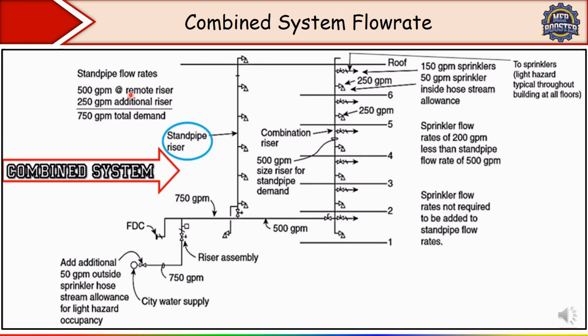You can also do the hydraulic calculation separately for the sprinkler system and for the standpipe. Now you have to see the flow value, whichever is larger, that we have to consider. No need to sum: the flow demand for sprinkler does not need to be summed with the standpipe demand. Whichever is greater, we have to consider. So is it clear? Now here you can see this 750 GPM is our total demand. As per that we have to do the selection. Clear?